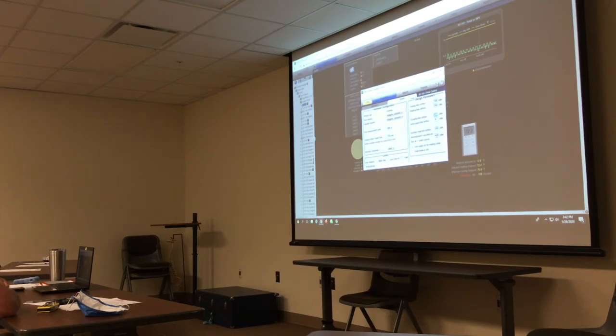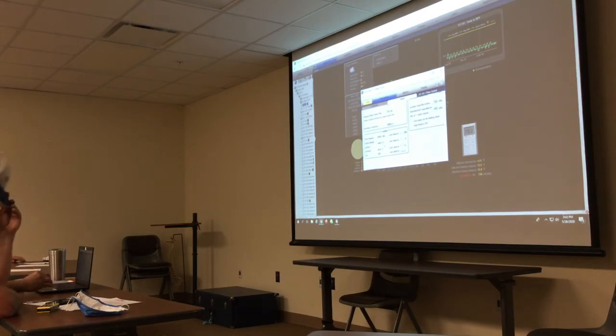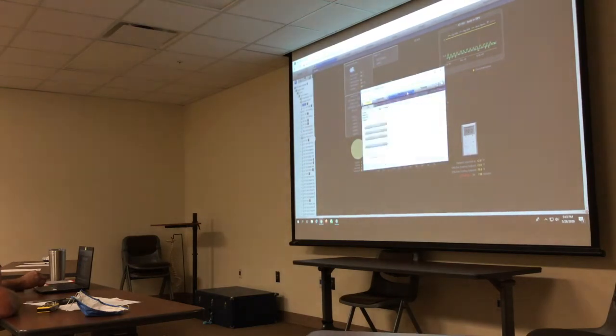If you're just wanting to override it, you can do it on that summary screen, and you can override the airflow to a set point. You can essentially lock it at a certain set point or lock the damper at a certain position. And that's down on the bottom left, lock flow set point to X CFM. Yes. Got it. You do it on both pages, both the summary and that details, but yeah. So we can lock flow set point or we can lock the damper in a position. So everything that you control click on is going to bring up essentially the pop-up window from the logic screen. Any questions?